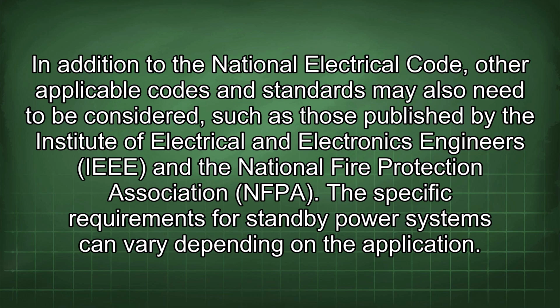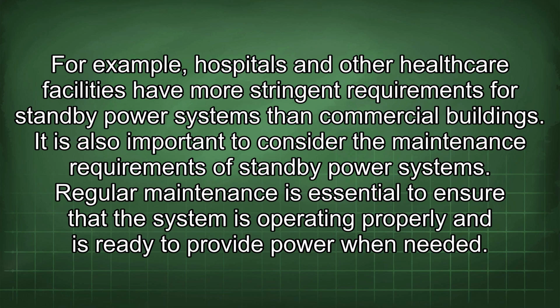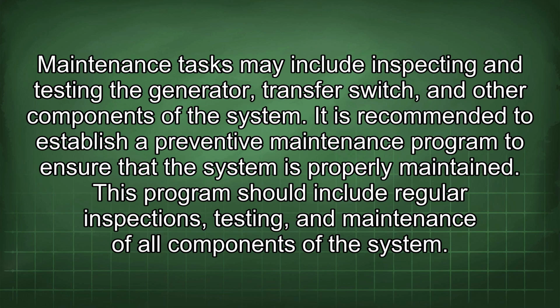The specific requirements for standby power systems can vary depending on the application. For example, hospitals and other healthcare facilities have more stringent requirements for standby power systems than commercial buildings. It is also important to consider the maintenance requirements of standby power systems. Regular maintenance is essential to ensure that the system is operating properly and is ready to provide power when needed. Maintenance tasks may include inspecting and testing the generator, transfer switch, and other components of the system. It is recommended to establish a preventive maintenance program to ensure that the system is properly maintained. This program should include regular inspections, testing, and maintenance of all components of the system.